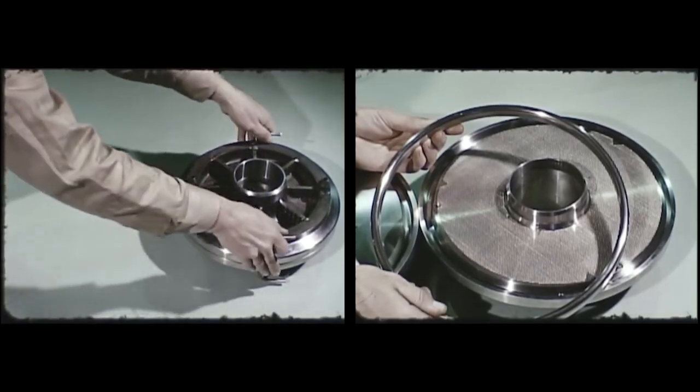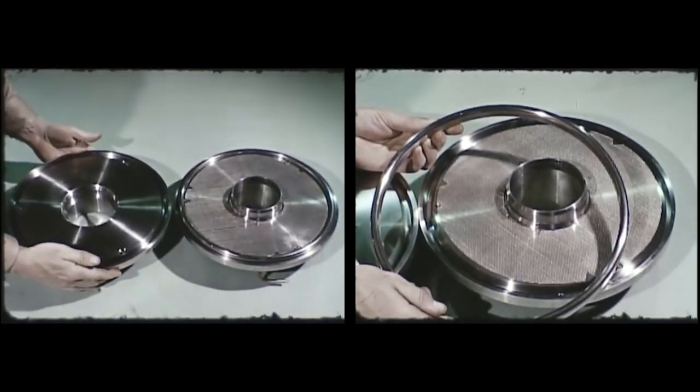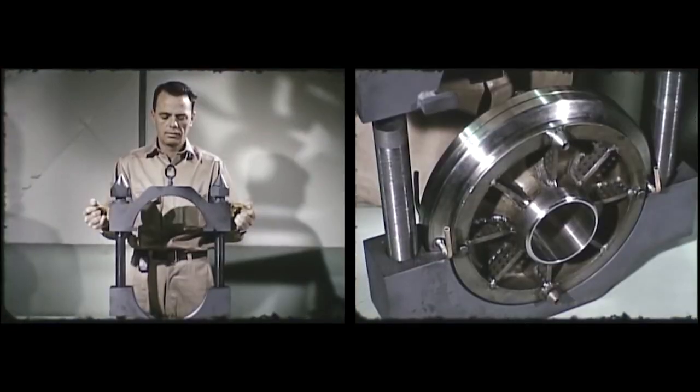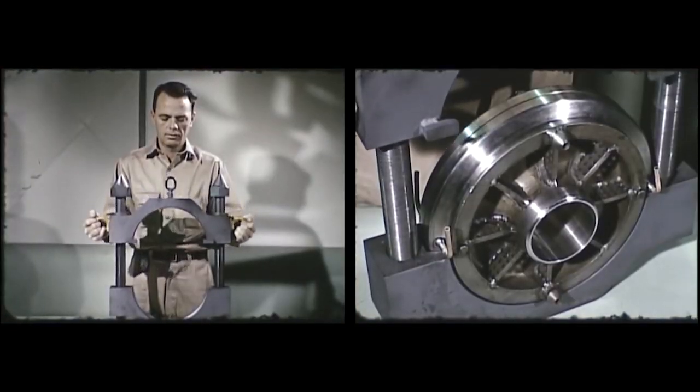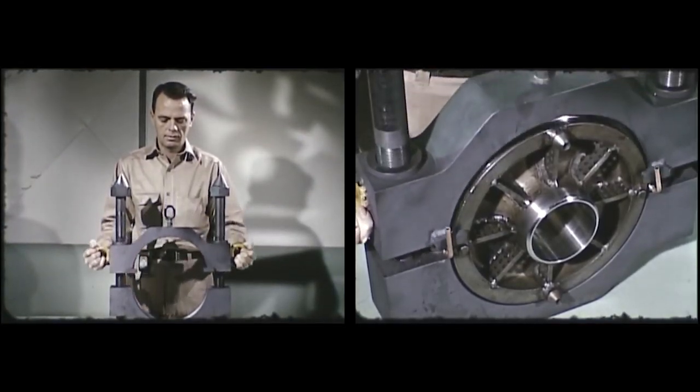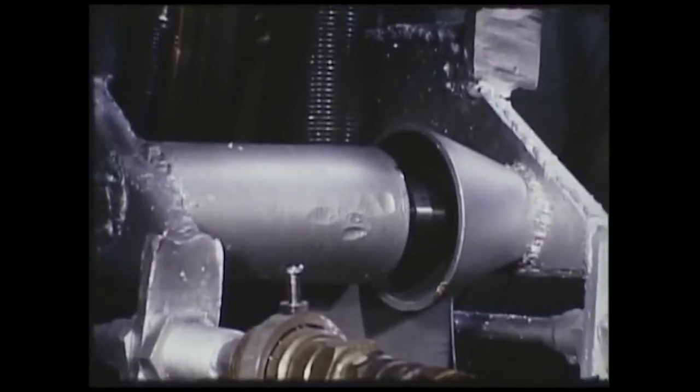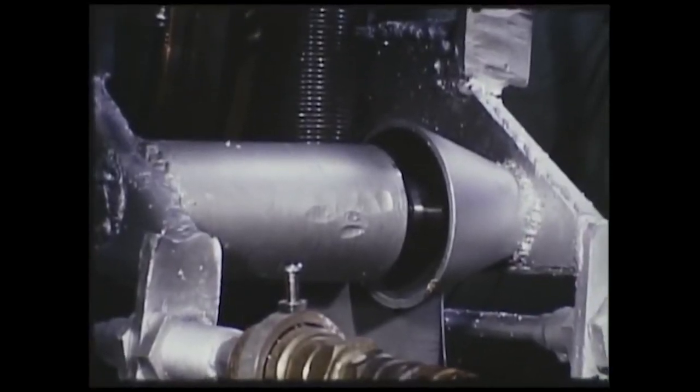This seal is backed up by a conventional metal O-ring which seals in the fission gases and serves as a leak monitor. Flanges are held together by two-section wedge clamps. A 16th-inch gap exists between the faces. It is in this volume that the salt seal is formed. Pin and funnel guides align the flanges during remote assembly.